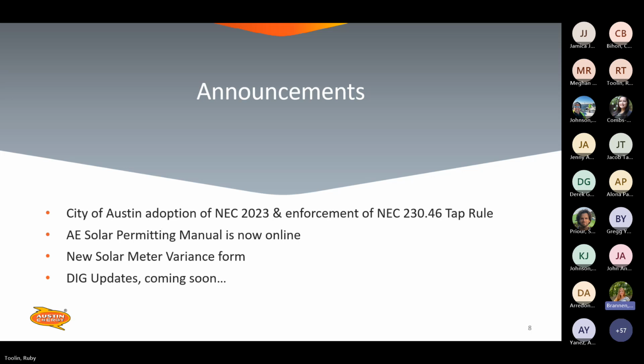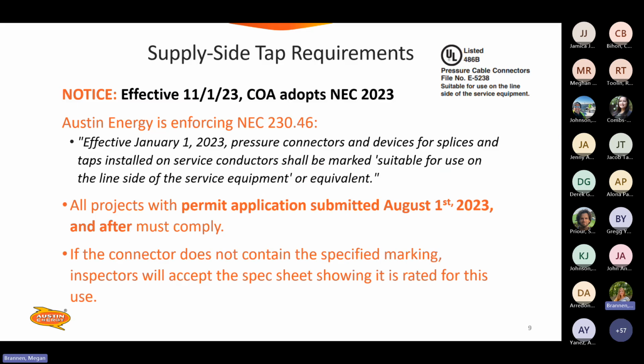All right, having said that, I'm going to try to get into some of the details here. So again, just keep in mind, we're on the NEC 2023 code now, and we are enforcing NEC 230.46. I'll just read this one so you guys have a reference to it. But effective January 1st, 2023, pressure connectors and devices for splices and taps installed on service conductors shall be marked suitable for use on the line side of the service equipment or equivalent. So make sure that they're marked, make sure that everything's compliant, and those are looking good.